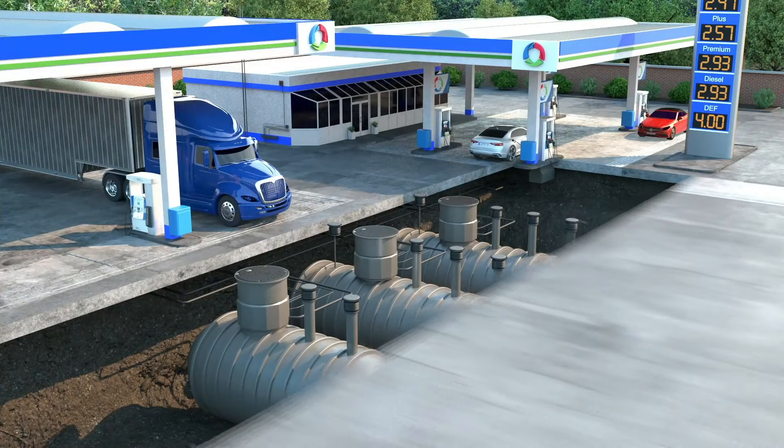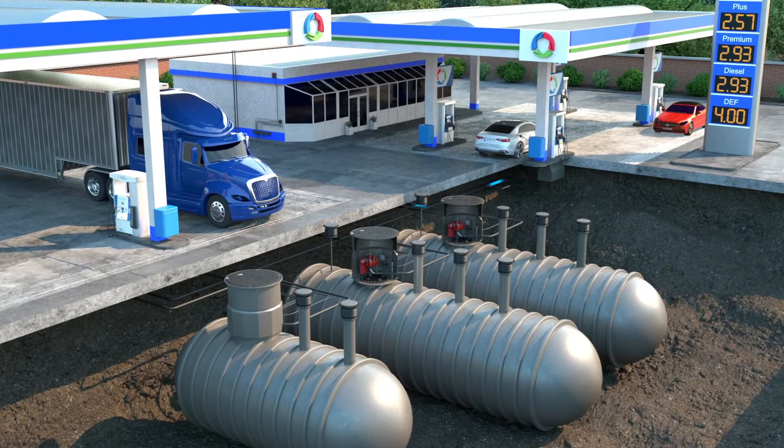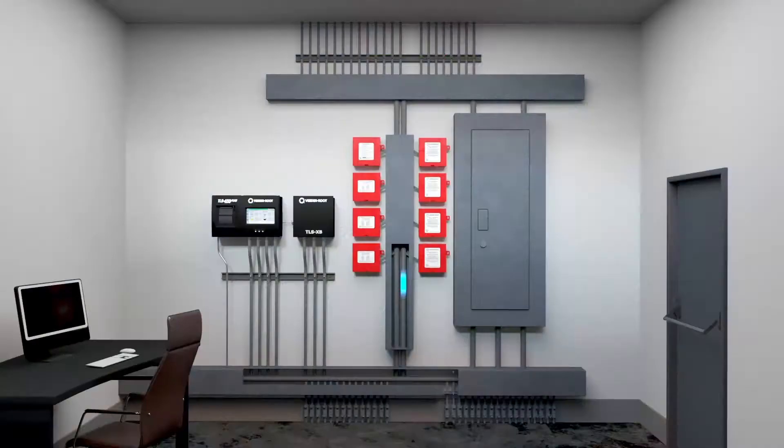Once the nozzle is removed from the dispenser, a signal is sent to the Red Jacket Isotrol control box, which isolates the signals between each dispenser and protects against wiring shorts and phasing issues.